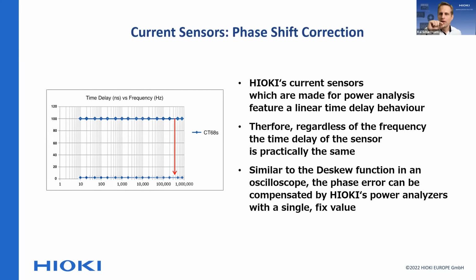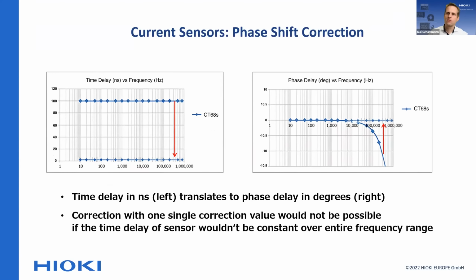And that's exactly what we can also do, because we have this constant time delay. If we have this correction value of 100 nanoseconds, we can apply it for every frequency. And 100 nanoseconds at a very low frequency is nothing. At a very high frequency, of course, it makes a big difference. So the fact that we have the same time delay over the whole frequency band allows us, with one single correction value, to correct this phase delay or phase error that is caused by our sensor circuitry. That's the big thing, what we call phase shift correction, because that is a feature that we have in our power analyzers as well.